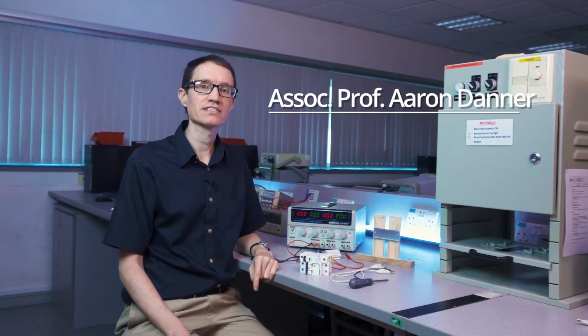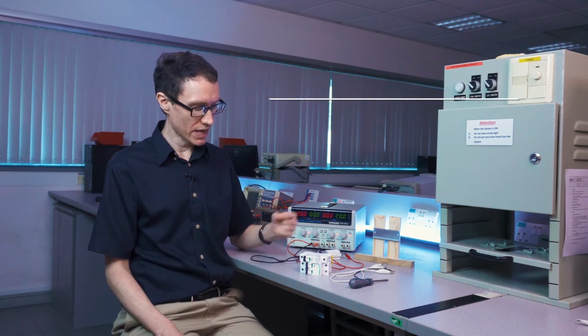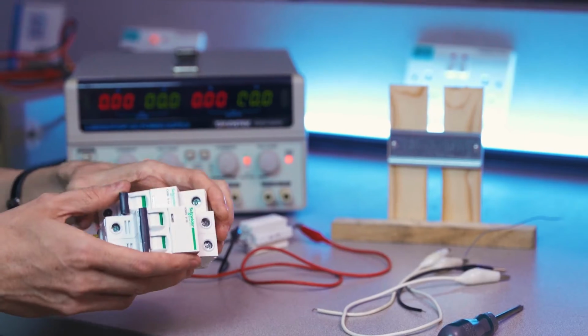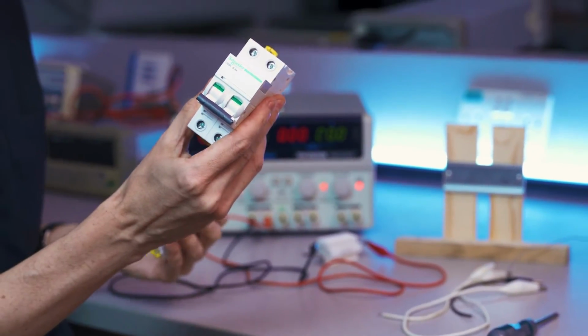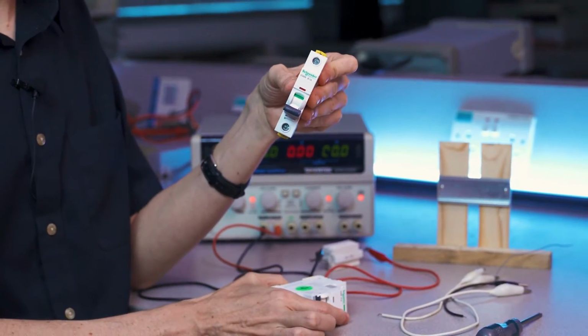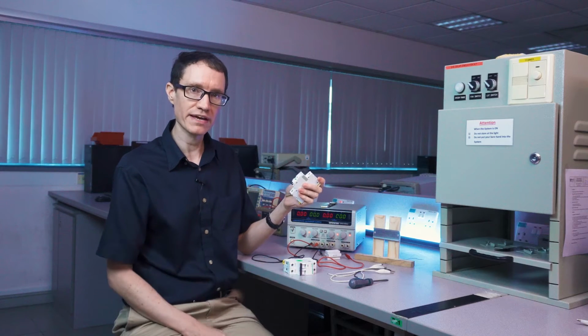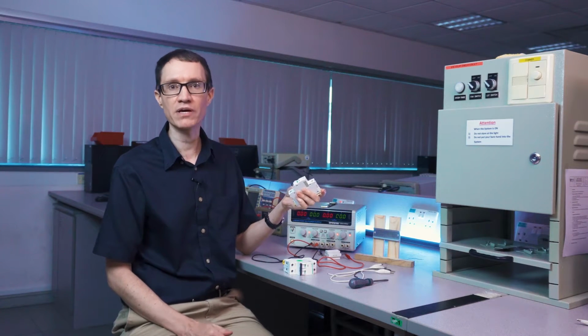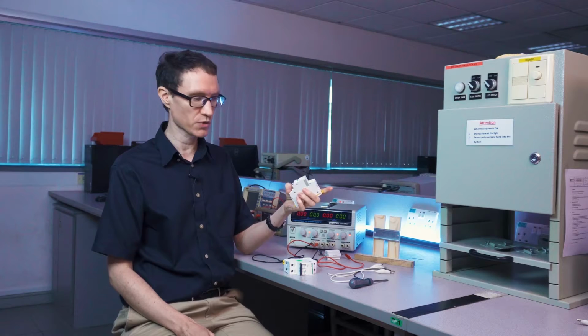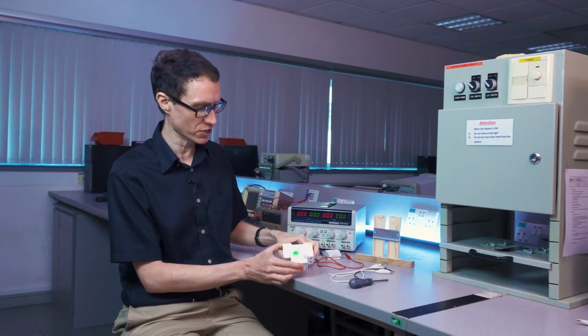We're going to be testing circuit breakers in this video. I have two circuit breakers here in front of me. This is a 2-pole circuit breaker, and this is a 1-pole circuit breaker. We're only going to be testing the 1-pole circuit breaker, but I do want to explain what the difference between these two types of circuit breakers is.